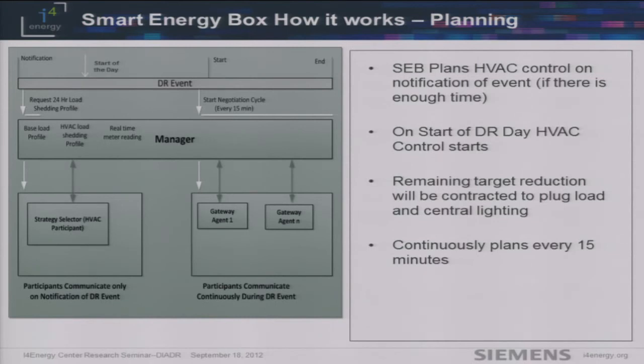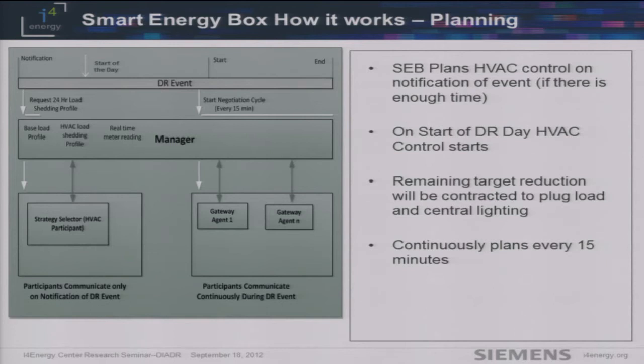When the event starts, the HVAC strategy will have already done some pre-cooling, bringing the building into a comfortable mode even after raising temperature set points. When the event actually starts, the manager looks at the real-time meter reading to determine how much energy still needs to be shed. There is a goal defined — for example, 30% or 20% of the base load. If there is still a goal to achieve during the event, it starts communicating with plug load components.